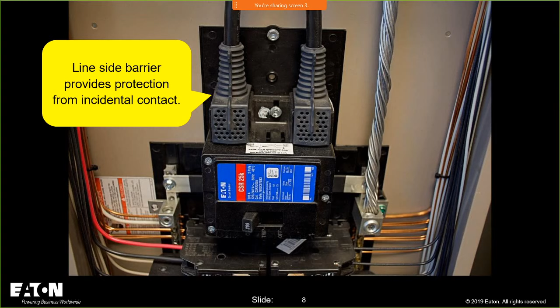What you're seeing from most manufacturers, I call them booties, but they are barriers, line side barriers. Put the barriers on, and I would say these barriers can be used not just on the service entrance panel boards. They have a lot of value on any downstream panel board where you have a main overcurrent protective device in that panel board. This provides some level of protection.